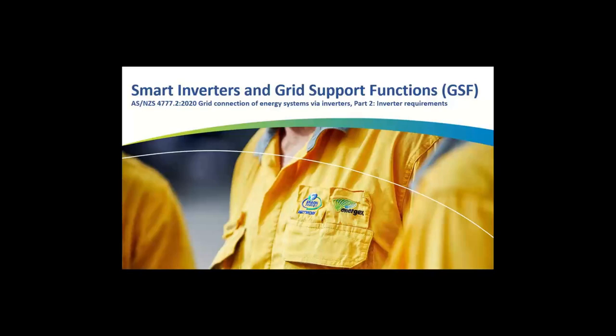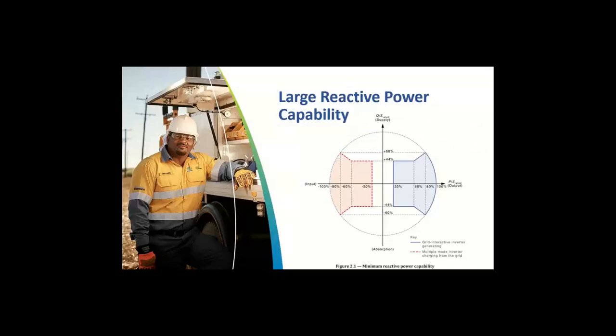The second thing I wanted to touch on today is the grid support functions that smart inverters are now providing, in not just Australia, but also in some European jurisdictions and in some parts of the US, such as California and Hawaii. Power electronics, such as inverters, can not only draw or inject active power, which is shown here on the x-axis, but can also absorb and inject reactive power by adjusting the power factor and the phase angle between the voltage and current.